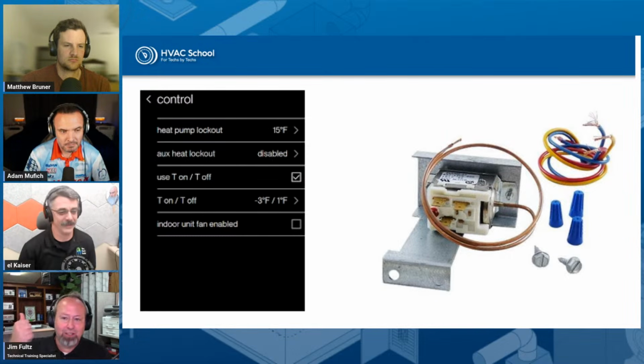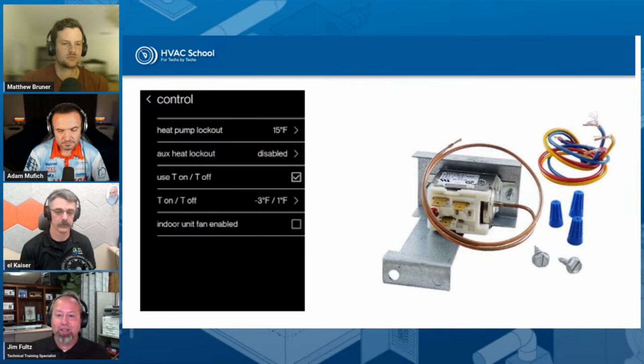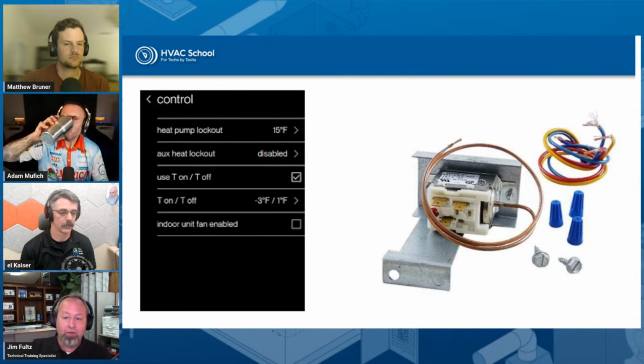Well, yeah, I should go back here on my shelf and grab one. Our Sensi Touch 2 now has a balance point built into it. So you can actually set a balance point at what outdoor temperature you want that resistance heat to cycle on for you. And that's based off of, it's a Wi-Fi thermostat, so it's getting your zip code and your local outdoor temperature from that. It could be within a degree or two, depending on where you're at. But that thermostat does have the ability to cycle the resistance on and off when you hit that balance point, and or you can shut off the heat pump if you want to.